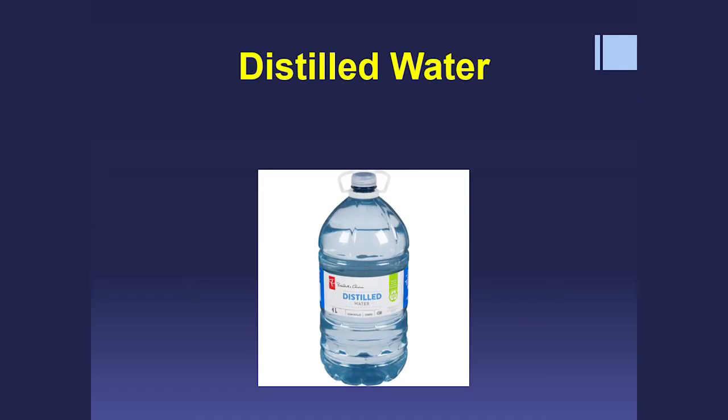Then again, one important point is which water we should use inside this autoclave. If you are using a class B autoclave, the manufacturers have already made such a provision inside the autoclave that you have to use distilled water, otherwise the procedure will not be proper. Many people get confused between distilled water and RO water. Tap water is not distilled water, everyone knows that, but many people have confusion between filtered water or RO water and distilled water.